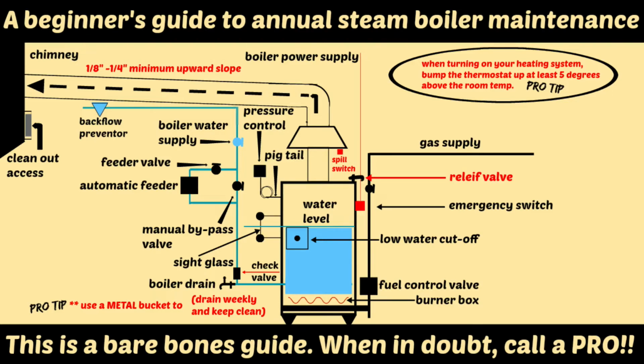And actually, when the water starts coming out of that bottom sight glass valve or sight glass cock, I will get a metal rod and shove it in there. I'm going to skim some of that dirty water off of the bottom of the gauge glass cock, and I'll get a bucket and stick it under there. I will leave the bucket there until the water runs relatively clean. At that stage, I'm going to put that valve back together again, and I will install my new glass gauge.